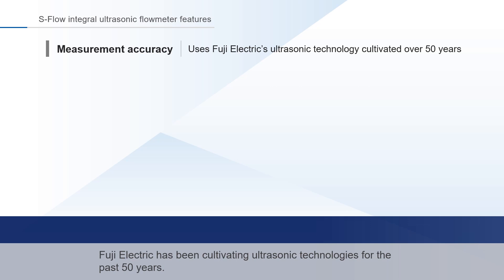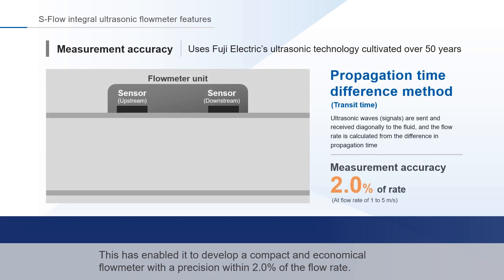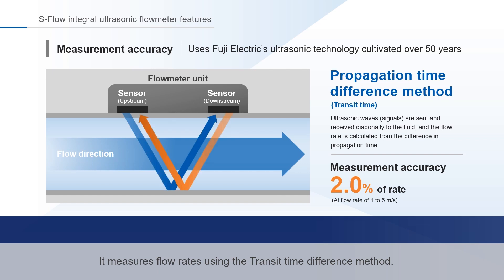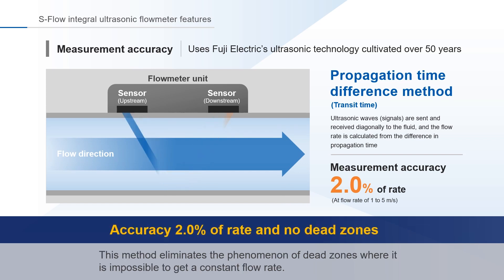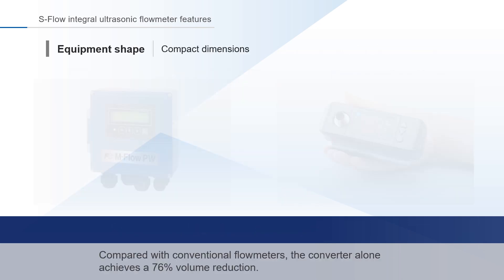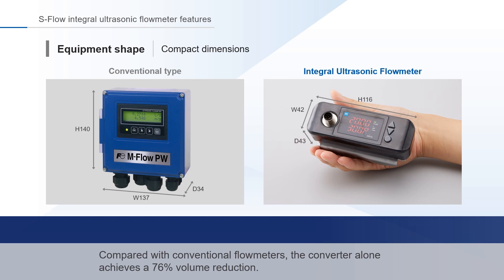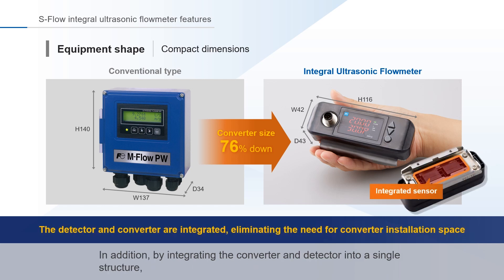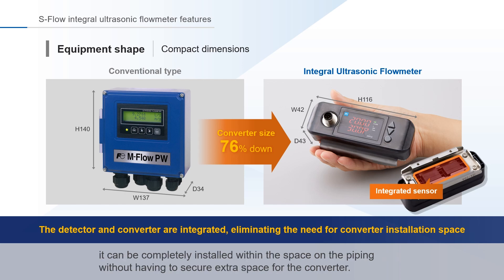Fuji Electric has been cultivating ultrasonic technologies for the past 50 years. This has enabled the development of a compact and economical flow meter with a precision within 2.0% of the flow rate. It measures flow rates using the transit time difference method, which eliminates dead zones where it is impossible to get a constant flow rate, making it possible to measure from zero. Compared with conventional flow meters, the converter alone achieves a 76% volume reduction. By integrating the converter and detector into a single structure, it can be completely installed within the space on the piping without having to secure extra space for the converter.